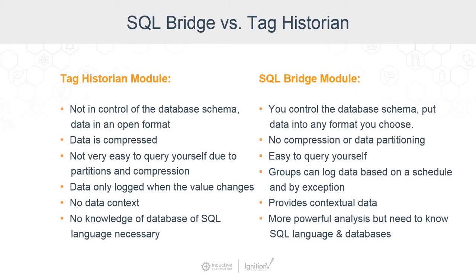We do lose a little bit of data context since we're simply logging each tag individually to a database. Now, with the SQL Bridge module for historical logging, you can control the database schema — you can put the data into any format that you choose, create your own tables, and map data into stored procedures or any other format you'd like. There's no compression or data partitioning, so we're not taking advantage of those features, but we're putting more of the power into your hands. The more you know about databases and SQL, the more powerful analysis you can get from your data, and you can also provide more contextual data.